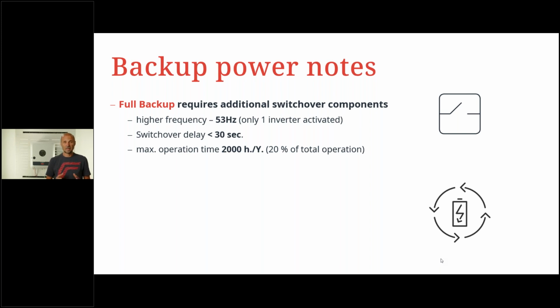So there is some time, of course. And fourth, we have a maximum operation time in backup power mode of 2,000 hours per year, so on average about 20% of total operation. This is in terms of the warranty. So please take care that you don't actually use the inverter in an off-grid system, because if we would see after 3 years that this inverter has run 100% in full backup power mode, we would probably not give you the full warranty.